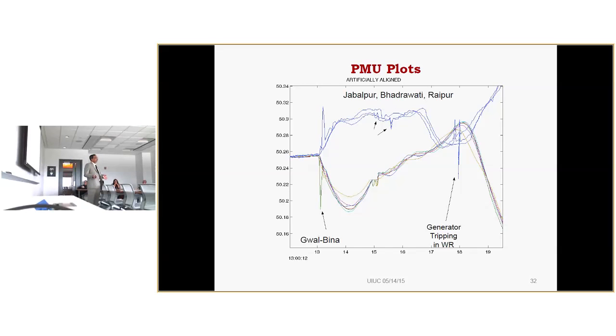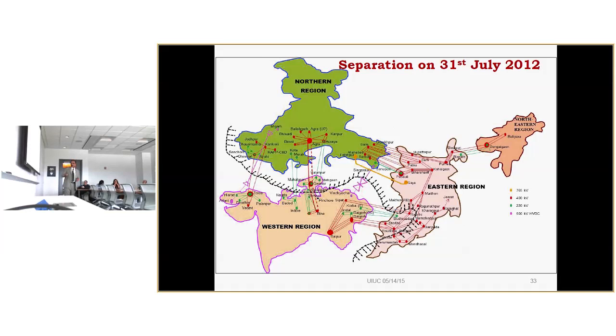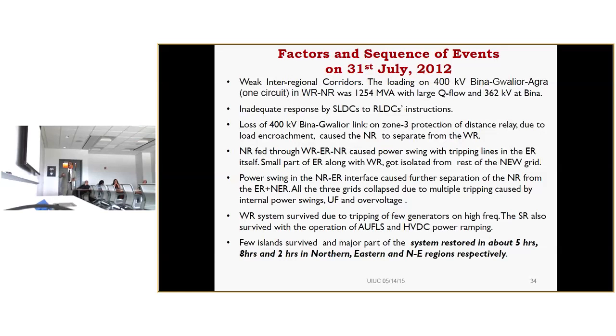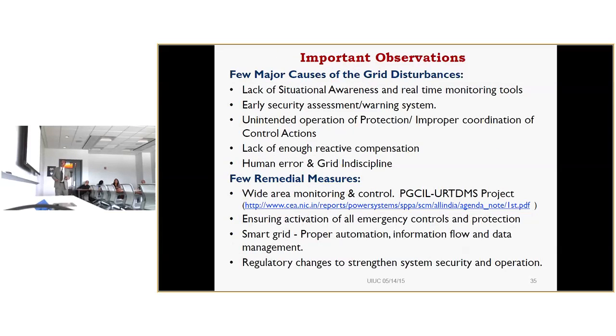So then the committee strongly felt the need for some system which can give dynamic visualization. This is the second day, the center of oscillations, and this part was under blackout. You see here the Q flow was high and voltage was low. And again there was encroachment of the relay because of load encroachment, and then subsequent firework. So an important observation was that situational awareness was not there. We don't have a proper monitoring tool. Then security assessment we cannot make.